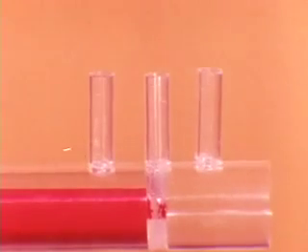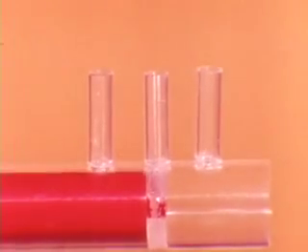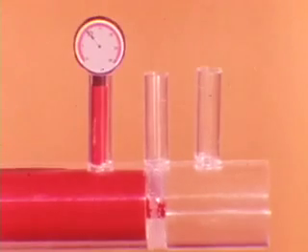Pressures in a moving liquid are much different than pressures in fluids at rest. Let's say we have a liquid being pumped into a tube and there is a restriction in the tube, a small hole properly called an orifice. Until the area in front of the orifice fills up, the pressure will be zero. Then it will climb to a value dependent on the pump pressure and the rate at which the liquid flows through the orifice.